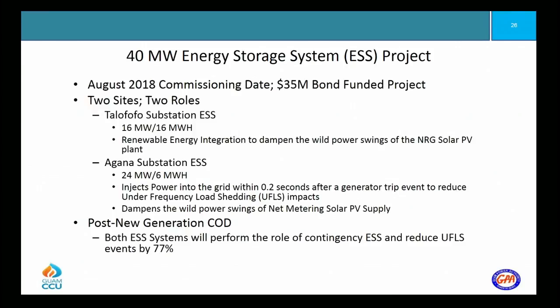If you recall, sometimes we have short interruptions of power, 5 to 10 minutes or so, that's when we lose a generator. The others cannot move fast enough to avoid the power outage, so we have to load shed certain areas to stabilize the system and not go into a blackout. By not going into a blackout, we're able to restore everyone within about 5 to 10 minutes. That's the under-frequency relay scheme.